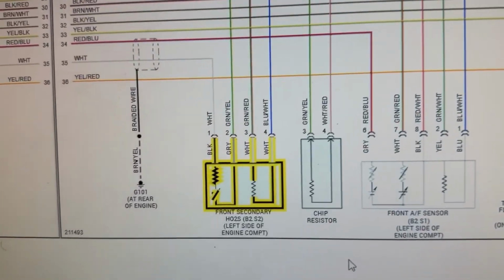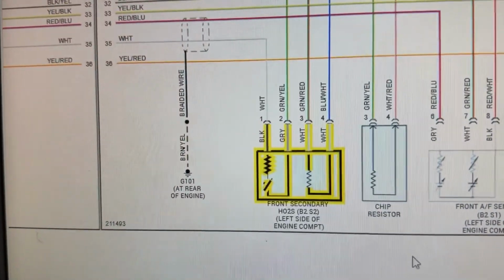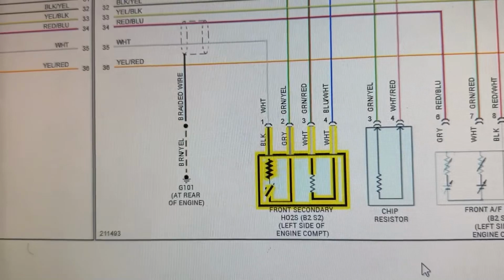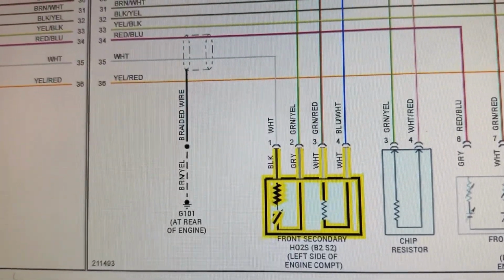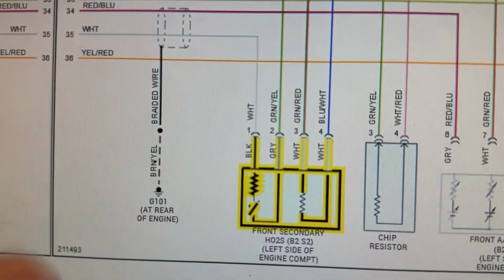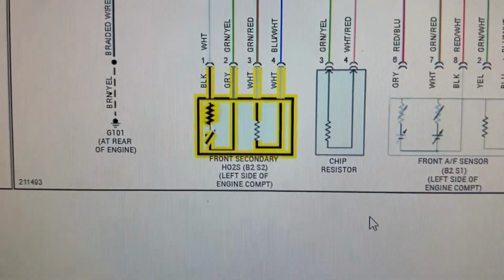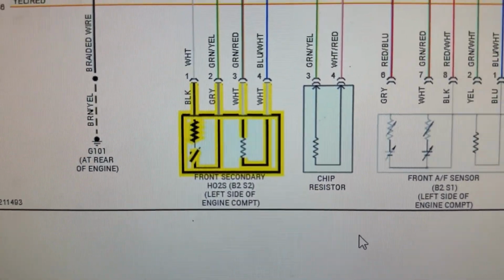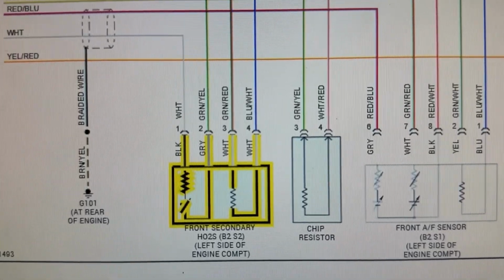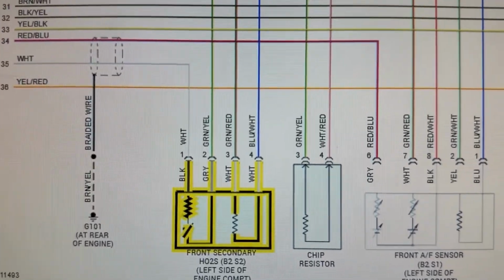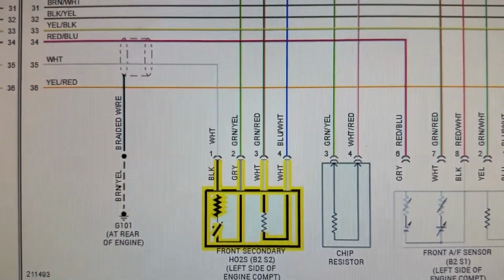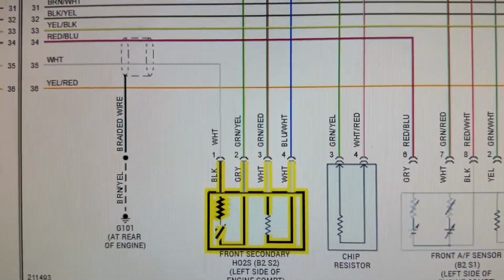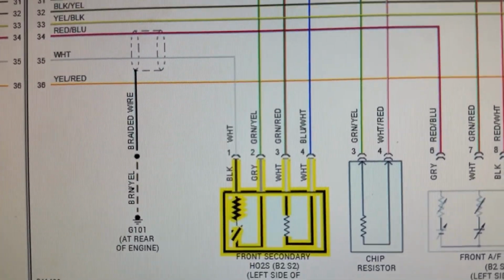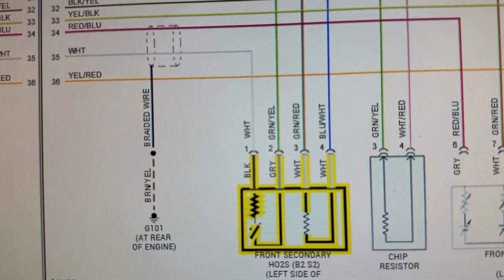Now we have the downstream sensor highlighted, and we're going to look at the wiring diagram for it. This white wire is going to be your sensor voltage. The green and yellow wire is your sensor ground. The blue and white wire is your heater power. And the green and red is the heater ground.